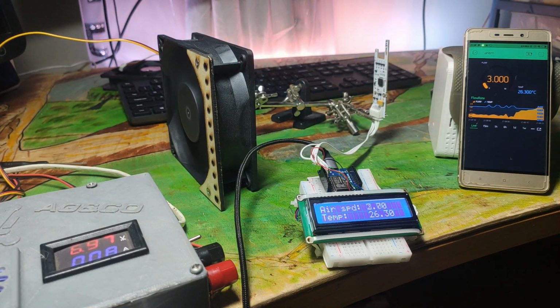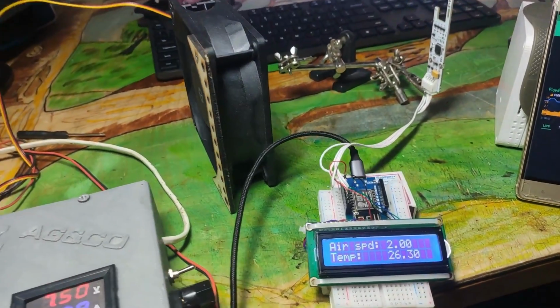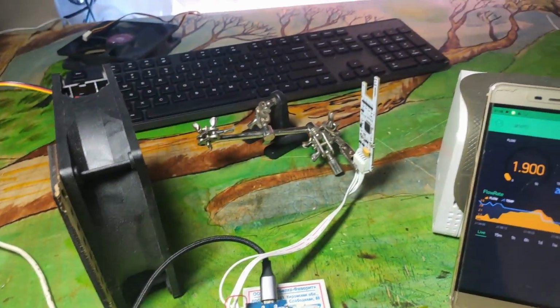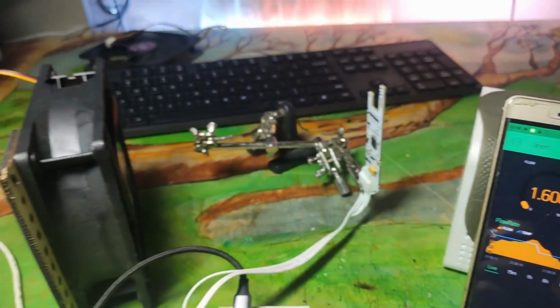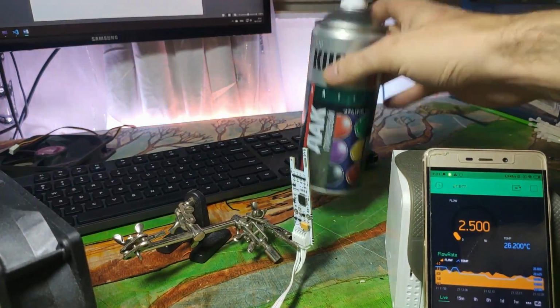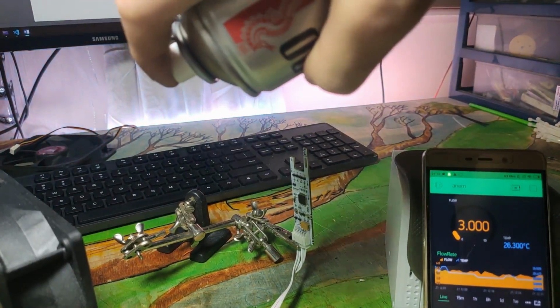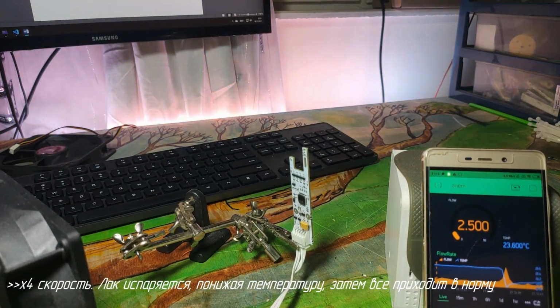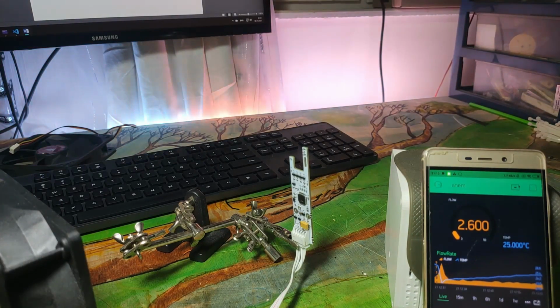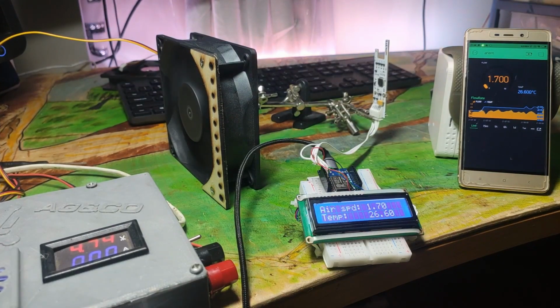After that, you need to fixate your device in the pipe in such a way that both sensors are not adjacent to the pipe. In case of installation in an environment with a high humidity level, it is recommended to apply varnish either yourself or ask the manufacturer during purchase. The layer of varnish should be thin enough so it will not affect heat emission. After the device is installed, we can see the airflow rate and air temperature.